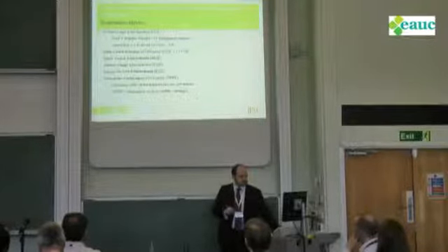The world average is around 1.9 at the moment. It is coming down because a lot more people are using the best practices to bring that ratio down. But I think it's pretty much appreciated that a target of about 1.5 is probably a good one to hit. Once you get below that, you start to hit the law of diminishing returns. The amount it costs you to get below 1.5 sometimes is not worth the savings that you're going to make. But you can make considerable savings.